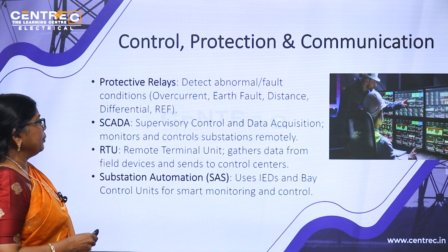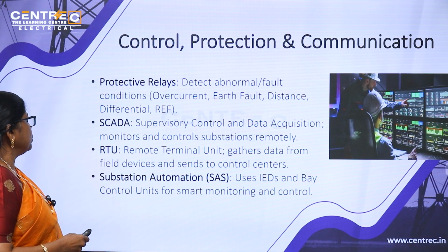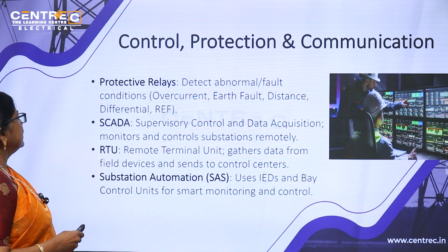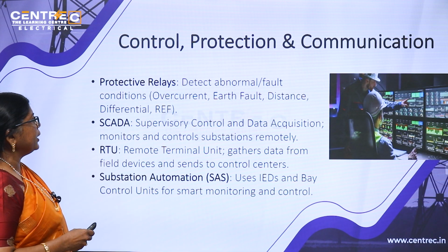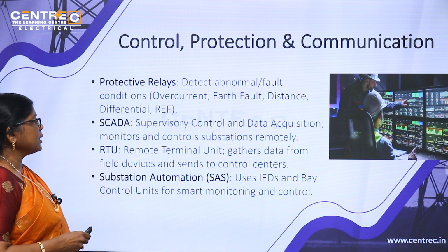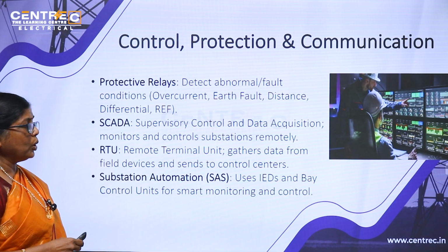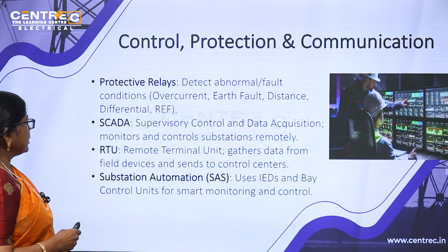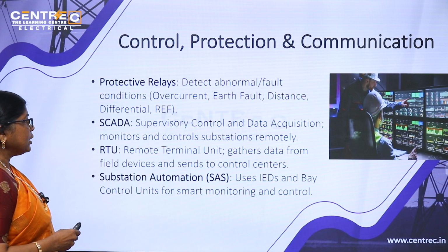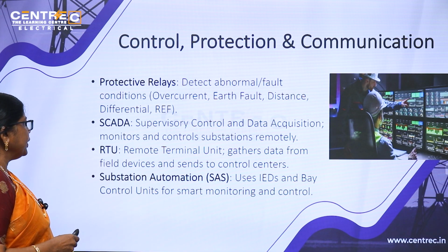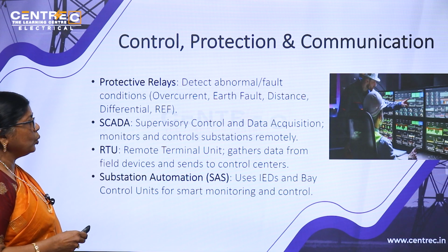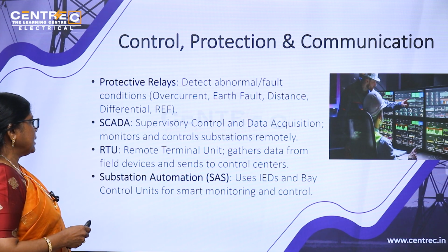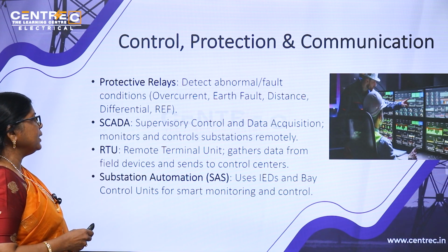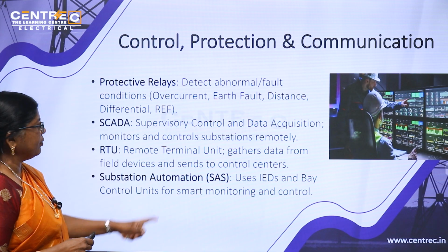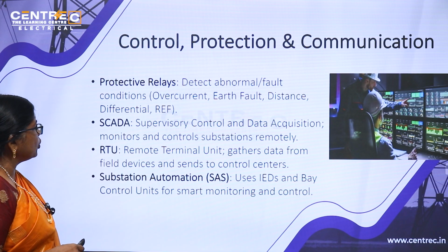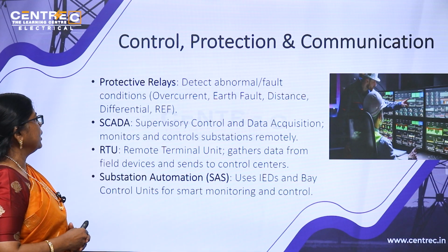SCADA is a modern technique to identify this system. Supervisory control and data acquisition monitors and controls the substation remotely. RTU, remote terminal unit, gathers data from field devices and sends it to control centers. Substation automation uses IEDs, intelligent electronic devices, and bay control unit for smart monitoring and control.